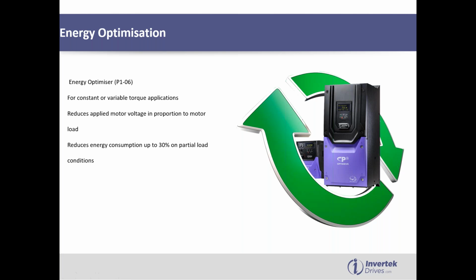We've also got the energy optimizer in the P2. So depending on the type of application you're using the drive for, you can turn it on or off. In the Eco drive, it's always on because that's specifically designed for quadratic or variable torque applications. But in the P2, you can switch it on or off as needed. And what it does, it monitors the output to the motor and the load, and then where possible, it'll reduce the motor voltage in proportion to the load. So you keep a constant speed, it's just you can save more energy, even on constant torque applications. The main energy saving for any VFD application is where you're running a pump or a fan on a partial load. And that's because of the nature of the actual load itself.